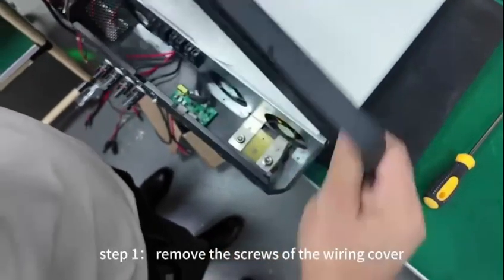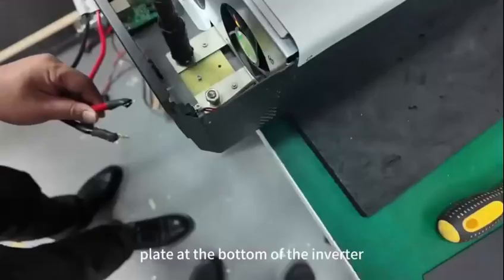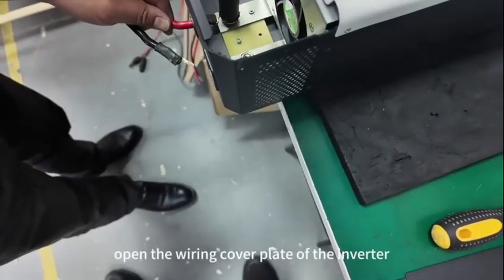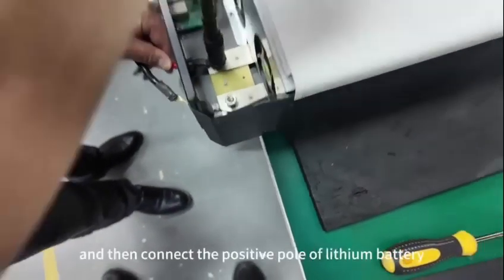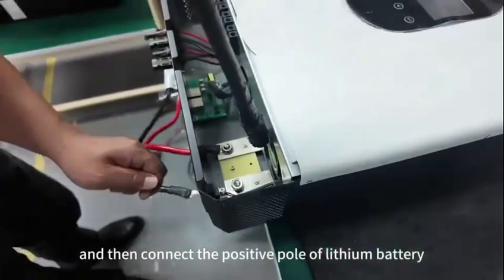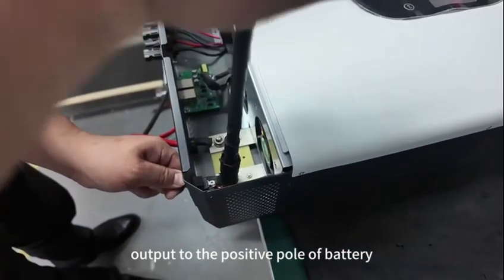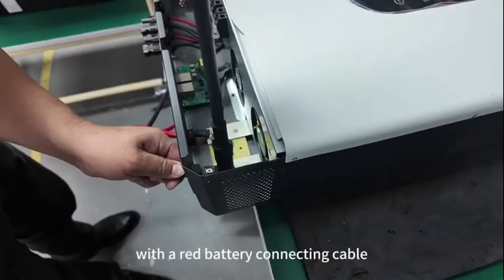Step 1. Remove the screws of the wiring cover plate at the bottom of the inverter. Open the wiring cover plate of the inverter, and then connect the positive pole of lithium battery output to the positive pole of battery input of inverter with a red battery connecting cable.